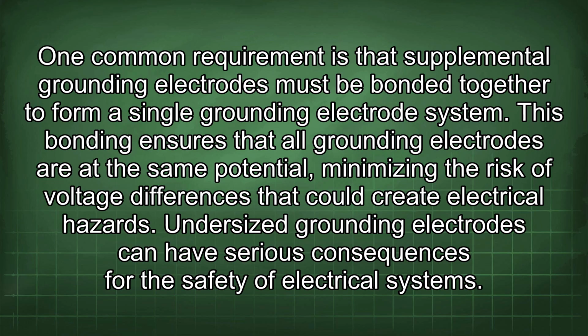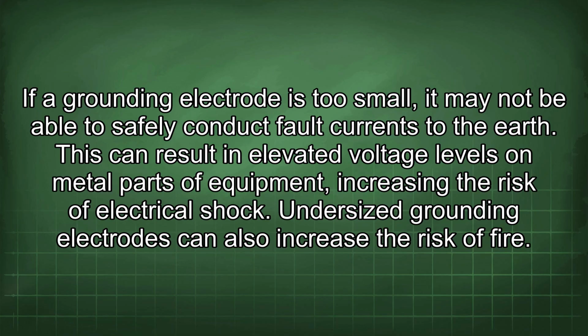This bonding ensures that all grounding electrodes are at the same potential, minimizing the risk of voltage differences that could create electrical hazards. Undersized grounding electrodes can have serious consequences for the safety of electrical systems. If a grounding electrode is too small, it may not be able to safely conduct fault currents to the earth. This can result in elevated voltage levels on metal parts of equipment, increasing the risk of electrical shock.